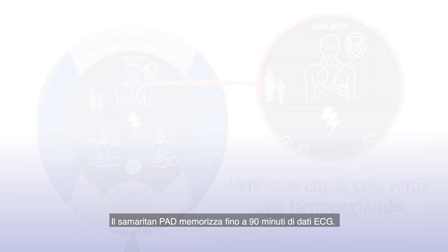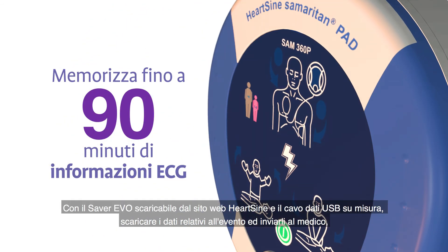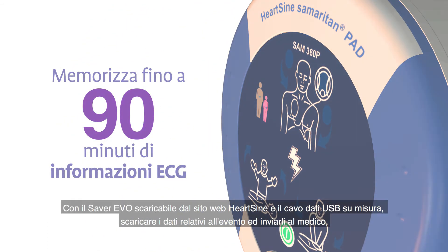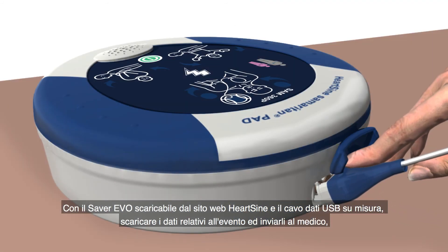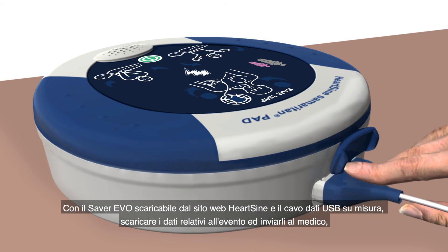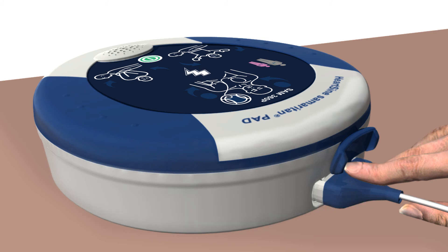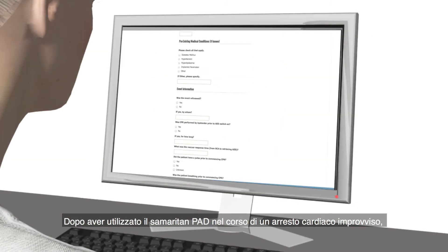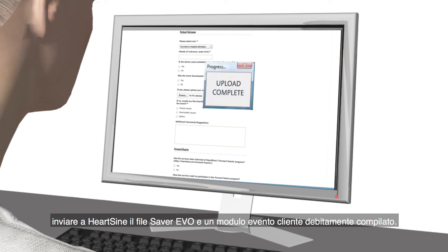The Samaritan PAD stores up to 90 minutes of ECG information after use. Use the Saver Evo software, which can be downloaded from the HeartSine website, and the custom USB data cable to download the event data for a physician who may want the information from the device to help inform treatment decisions. After using the Samaritan PAD during a sudden cardiac arrest, submit the Saver Evo file and a completed customer event form to HeartSine.